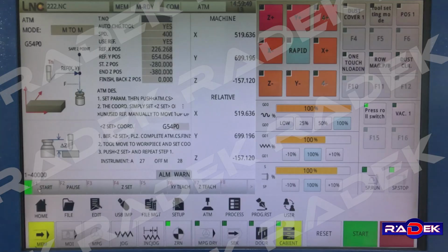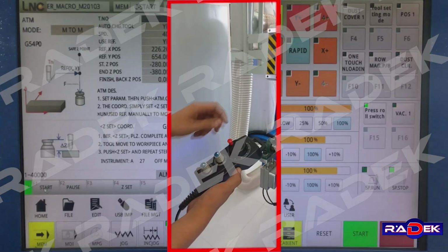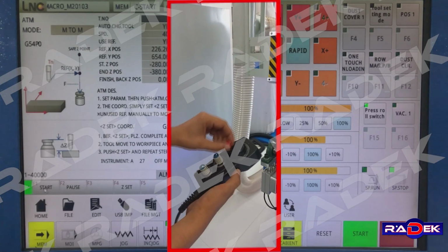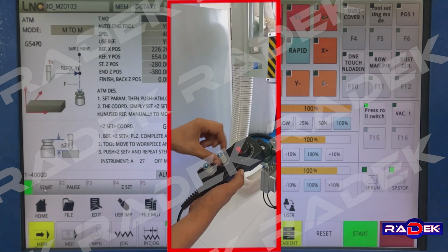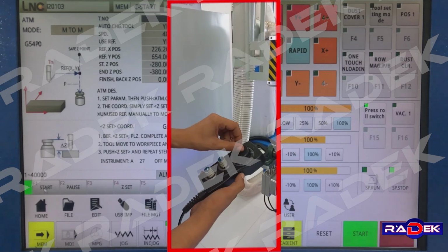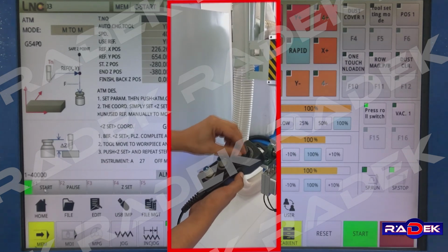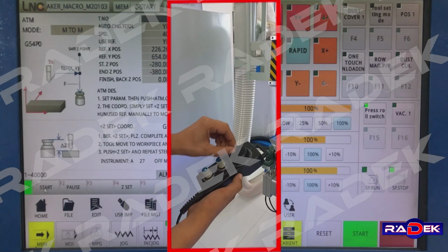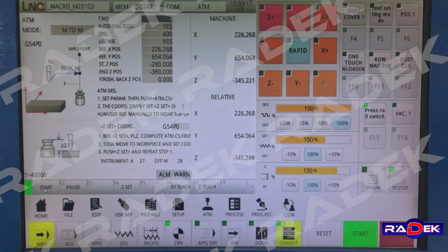After this, we will use the jog or the MPG function to reposition the tool so that it barely touches the surface of the material. The MPG mode is used when we want to move or reposition the axis, but instead of using their designated buttons in the interface, we will use the hand wheel controller, which offers more precise and smooth movements. With the help of the MPG controller, we position the tip of the spindle tool on the surface of the material, all while the vacuum pumps are running.